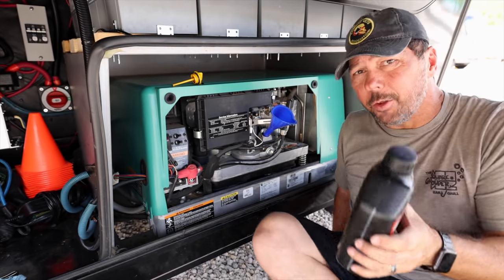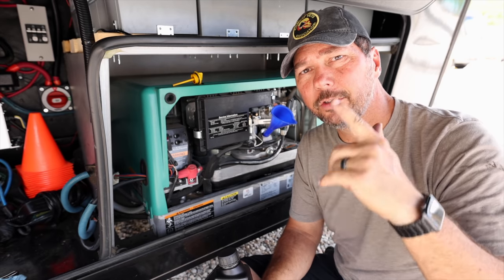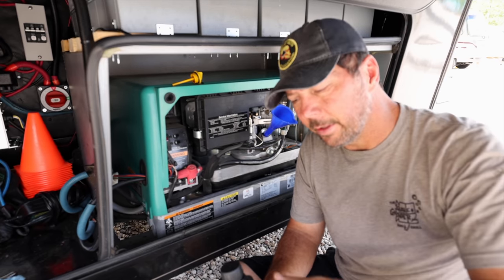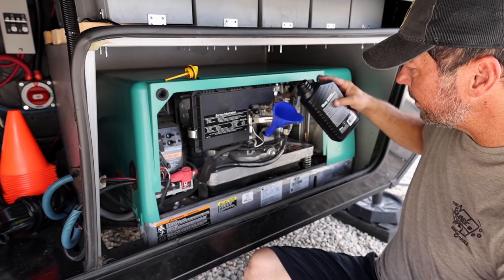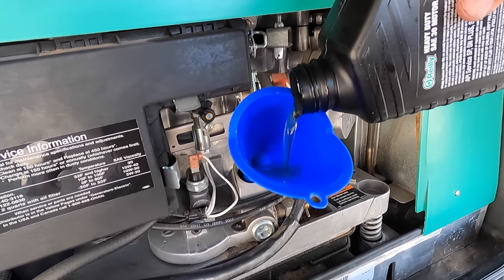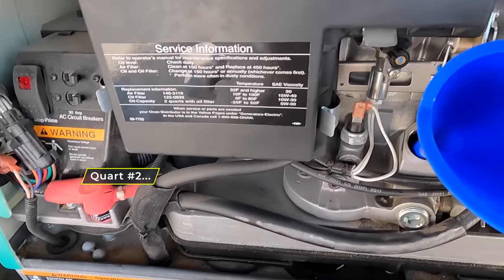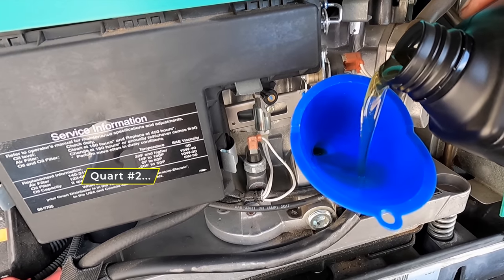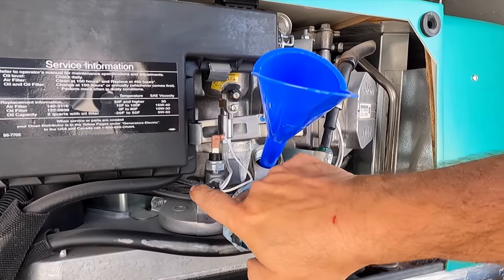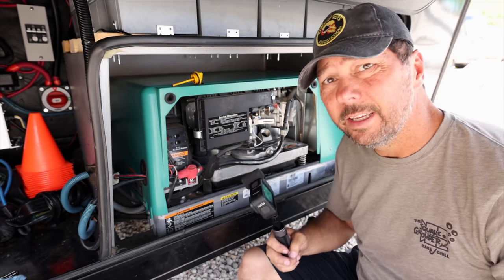The process here is to add the oil, run it for a bit, let it settle, check it, add more, run, settle, check. You want to get the oil circulated and then let it settle. I know from experience this might overflow a bit, so here's where I'll want to start paying attention for overflow. There it is — so I can't really add a whole lot more yet.